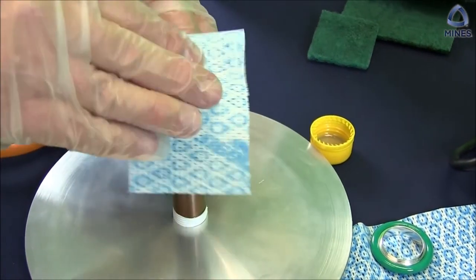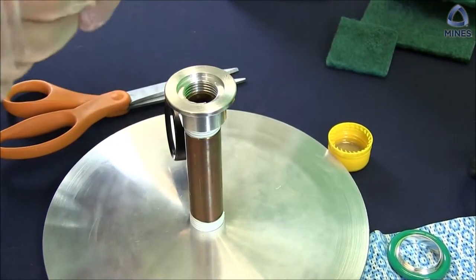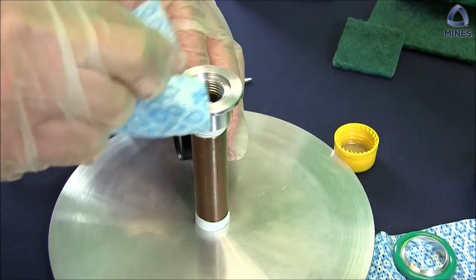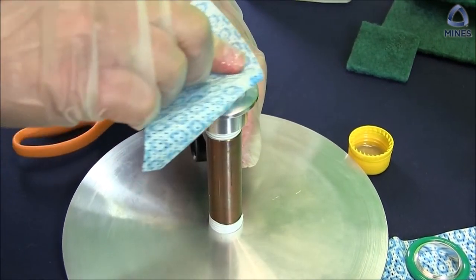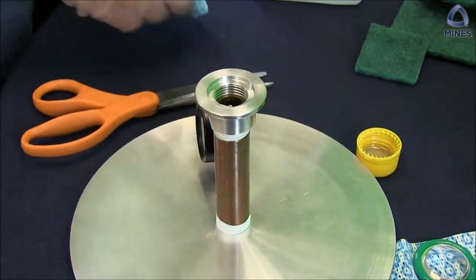Once the scratch has been leveled by polishing and the surface cleaned of the polishing media with a lint-free cloth, apply a small amount of clean vacuum pump oil to the sealing surface to help seal any remaining scratches.